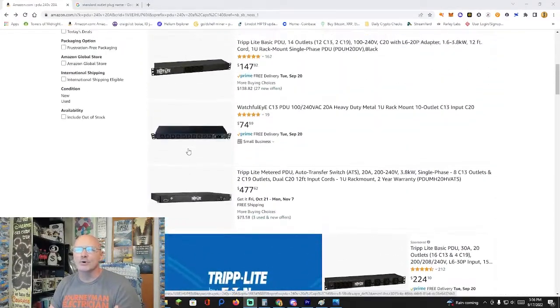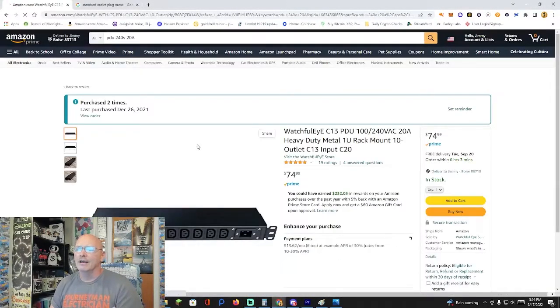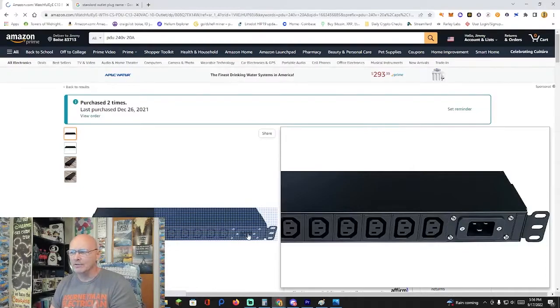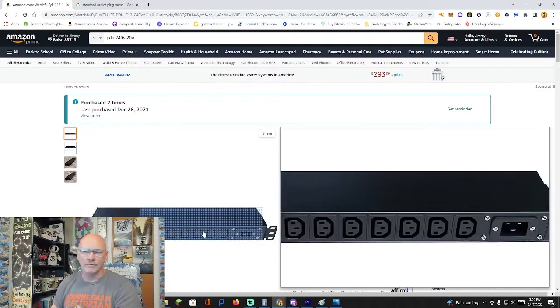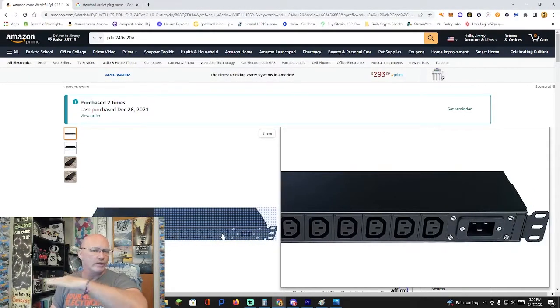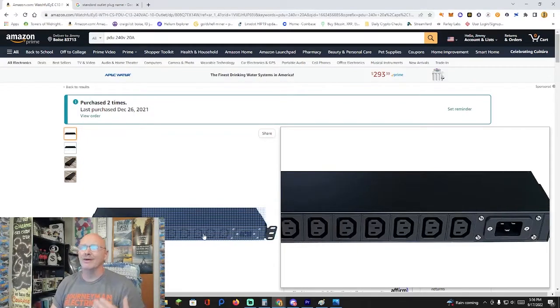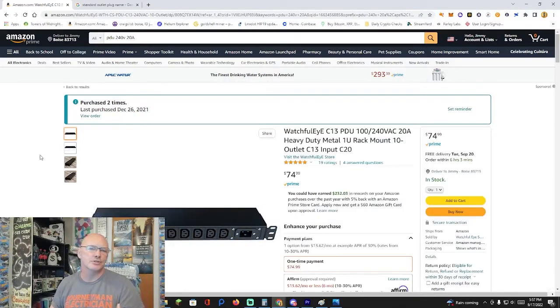So some of the simplest ones, like this guy right here. He's a straight up C20 for the power and a row of C13, C14s for the inlets. So that's pretty much good. Now, it doesn't have an inline surge arrestor. Kind of wish it did. But when I start hitting the price range of those guys of $300 and $400, I'm doing this on a pretty frugal budget. So you know what? I'm going to get the $75 one because I know my load calcs are good.